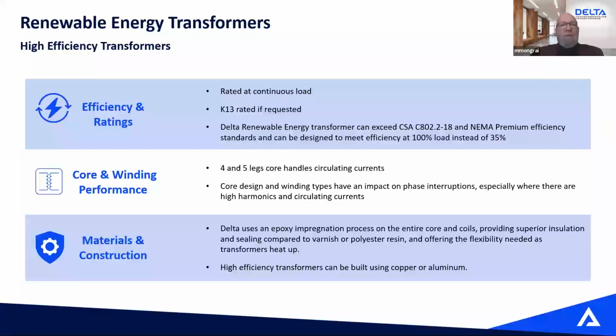So our proposal for a renewable energy transformer, it's not a product, it's a solution. So you can customize your transformer depending on your system. We offer different kVA ratings from 15 up to, we even do large power transformers. Depending on your inverter type and the harmonics generated by your inverter, we can even provide transformers with a K rating, K13 all the way up to K20. All of the transformers meet the NRCan efficiency requirement when they fall within the regulation. Some products are excluded from the efficiency standards, such as autotransformers and any type of fully enclosed transformer like epoxy potted or NEMA 4 transformers. Those are excluded, so they will be less efficient.